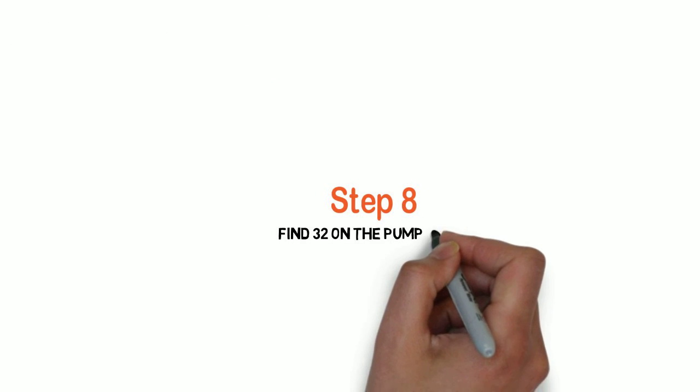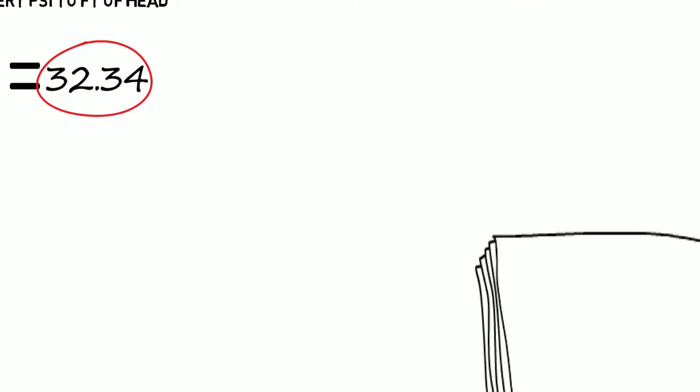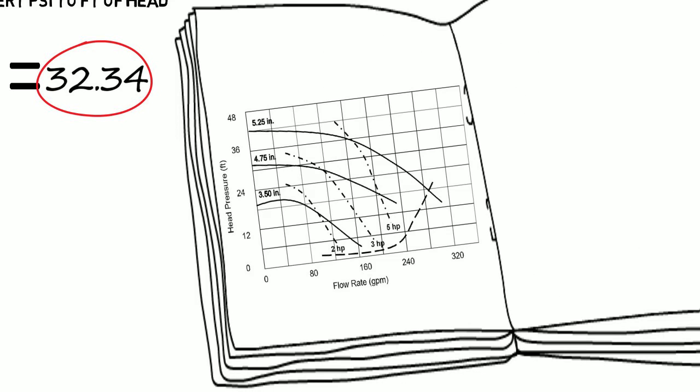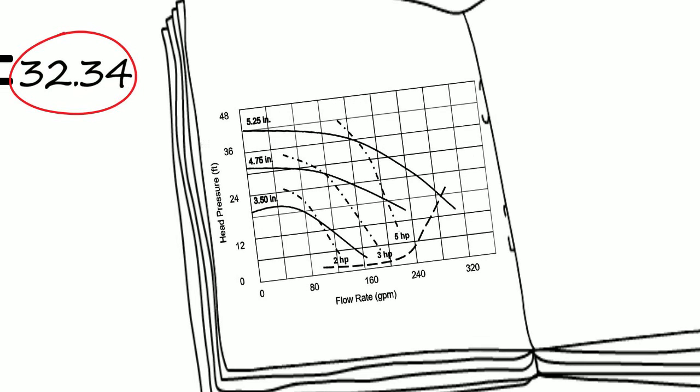Step eight, we're going to find 32 on our pump curve. Here's our pump curve. We find 32 on the left-hand column where it says pressure and feet of head, and it is between 24 and 36. There's the green dot. We draw a line over until it meets our impeller diameter, which was 4.75, and we track down to zero flow. That's perfect because the valve's shut. It's not moving any water. It should be zero flow.